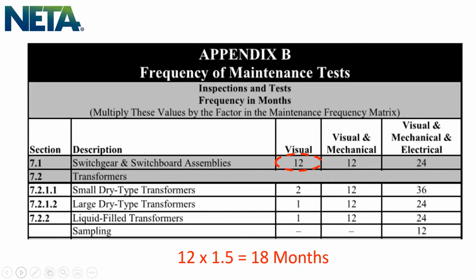For switchgear assemblies, I want a visual inspection once a year. Well, if you're at a good rating, we go times 1.5 and stretch that out to 18 months. Make sense?